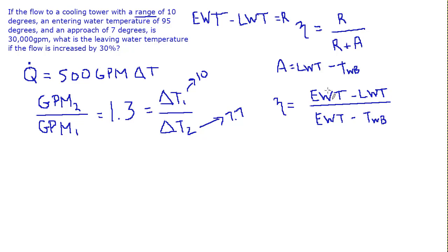So the numerator is how cold you're getting the water. It comes back and enters the tower. This is how cold you get it. This is how cold you could get it. If the approach approaches zero, then the leaving water temperature is approaching the wet bulb temperature of the air. And that would be the most efficient possible outcome. That would mean that this ratio would start to approach one, and you'd have 100% efficient cooling tower.